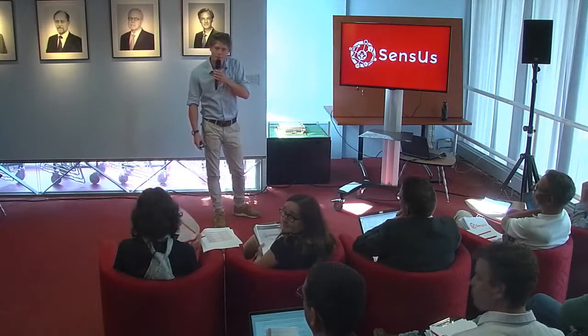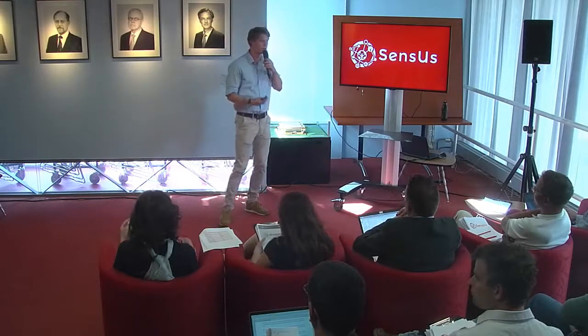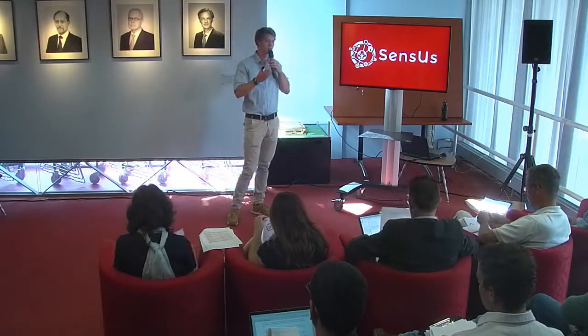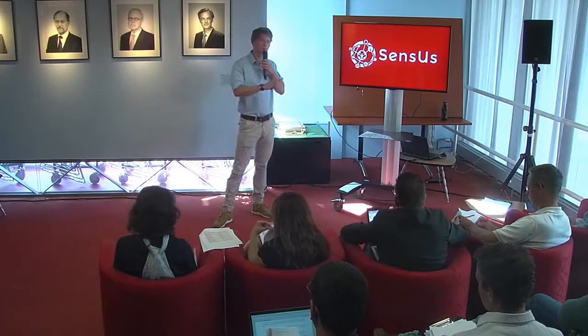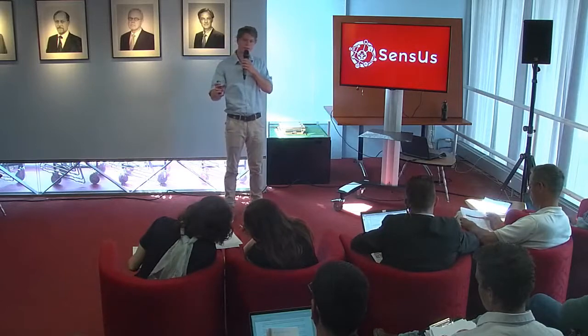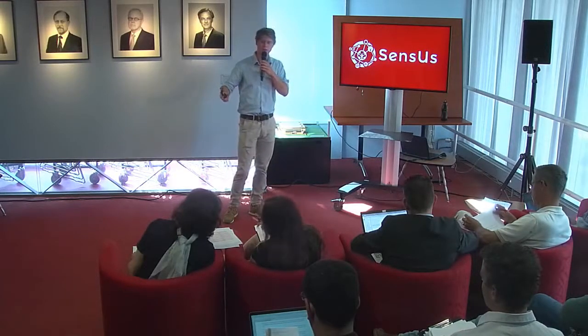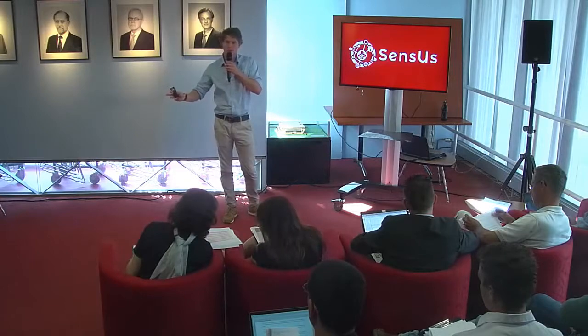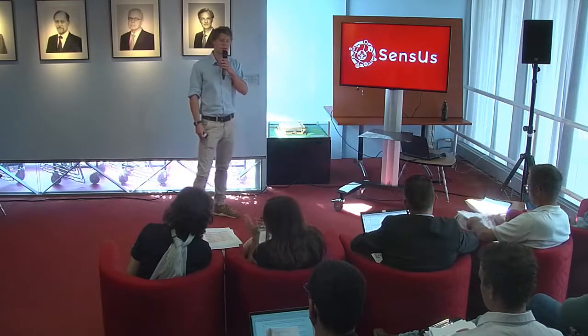I'm sorry. What was your question? Do we require cold storage for transport? Yeah. So we do right now because we use antibodies in our detection, and they have to be stored at minus 70 degrees. But we've also looked at different possibilities for using a D-Ala sequence, which is a part of the bacteria that vancomycin works on, and if the device detects D-Ala just as it does antibodies. So if we can replace the antibodies with that peptide sequence, then that wouldn't be necessary anymore. But that would, of course, require additional development of the assay.